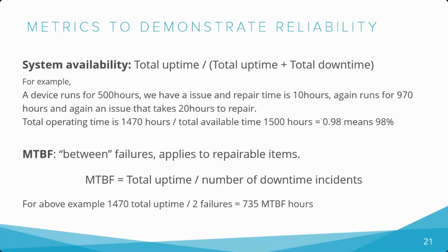Till now, I was walking you through introduction, definition, engineering responsibilities, analysis, application in new product development, and tools and methodologies. Various metrics are used to measure reliability and the probability of failure, including the following. System availability. This is the ratio of a system's actual operating time divided by the total amount of time it should be available, which is its uptime plus its downtime. The closer to one the number is, the better the availability, and the more reliable it is, because that would be equivalent to 100% availability.